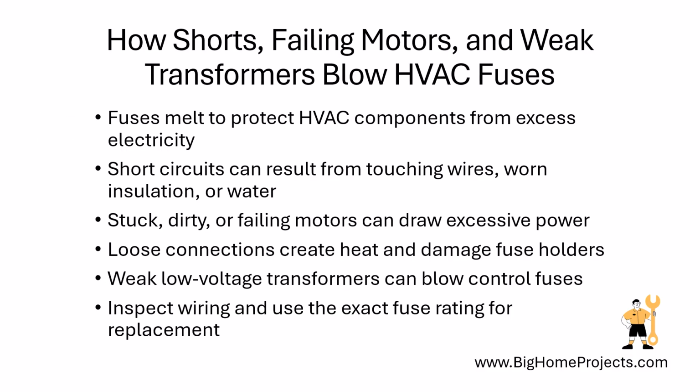In a heating, ventilation, and air conditioning system, this protects the control board, wiring, blower motor, outdoor unit, and other parts from overheating. A short circuit can happen when two wires touch, when insulation wears away, or when water reaches an electrical connection. A motor that is stuck, dirty, or wearing out may also draw too much power and cause the fuse to open.